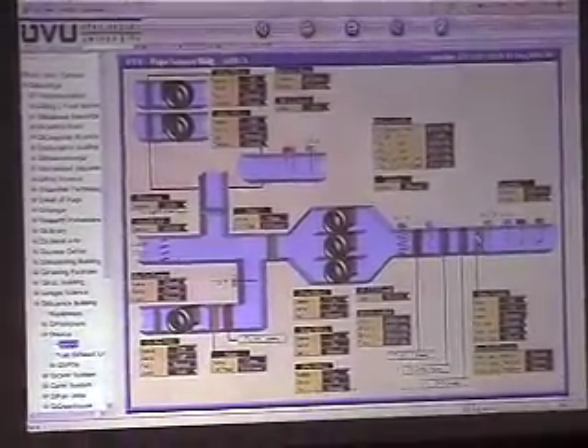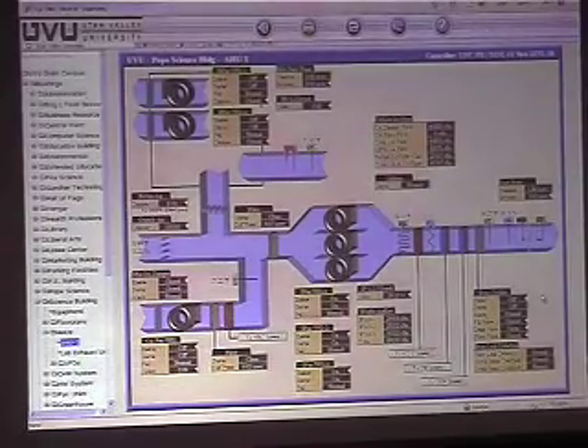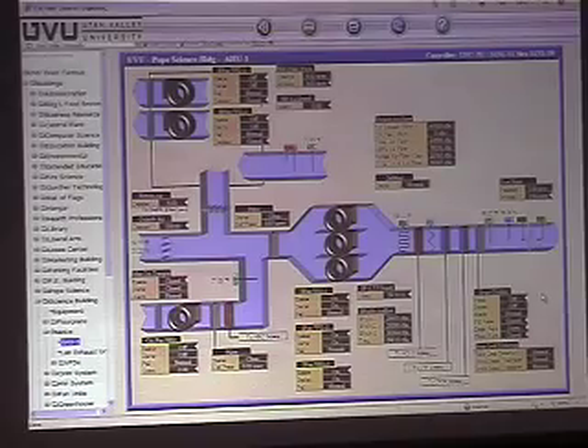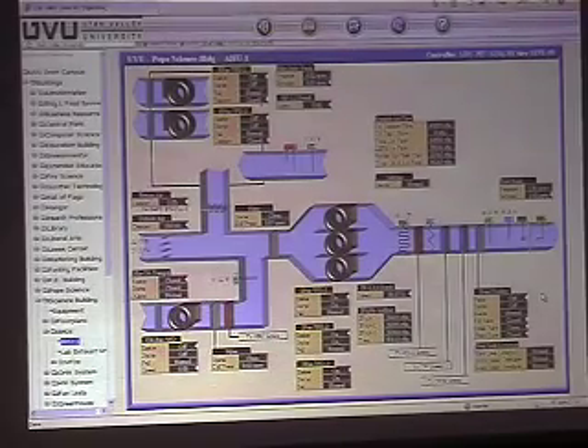So when there's a call for cooling in this portion of the system, it'll first open up the fill valve, and there's about a 15-minute delay before it'll turn on the pumps. The pumps have their own internal floats, so they won't turn on until the water's high enough anyway. But this way there's a little bit of a delay to allow the water to fill the sump up. And then once it does, it'll turn on the pumps and push the water up to the top of the evap media and circulate that down into the system. The fill valve stays open the whole time that there's a call for this, and there's a float valve inside the tank, and I'll show you how all that works when we go up there.